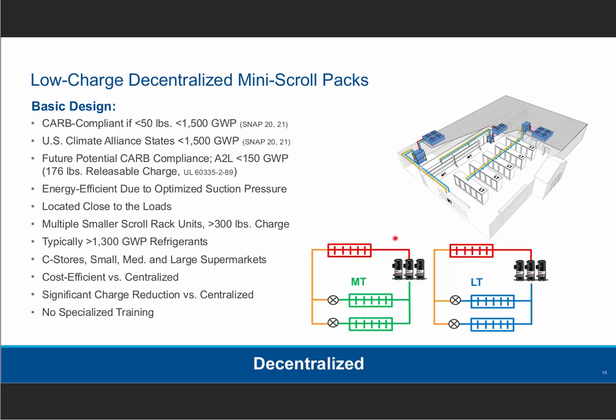My little schematic down here, my stick diagram, just represents a multi-scroll compressor rack, individual medium temp, and a separate individual low temp. And these architectures in Canada, of course, can be used with a GWP limit of 2200 with no charge limit, so that's not a problem. But what about California, for example? If you can get your charge down to less than 50 pounds come 2022, that's an option using SNAP-approved refrigerants, which started in 2019. Again, in the U.S. Climate Alliance states that have started to implement some dates, this architecture can be used based on the specifically allowed refrigerants.